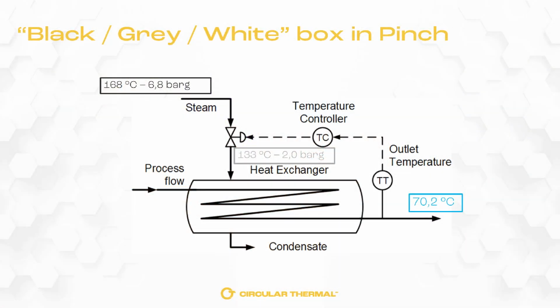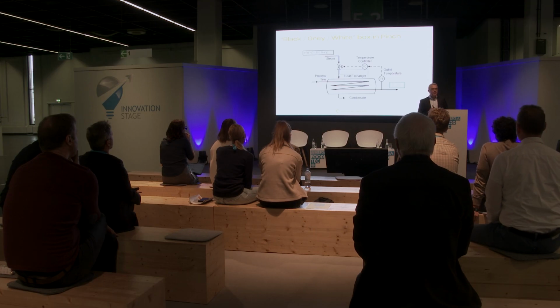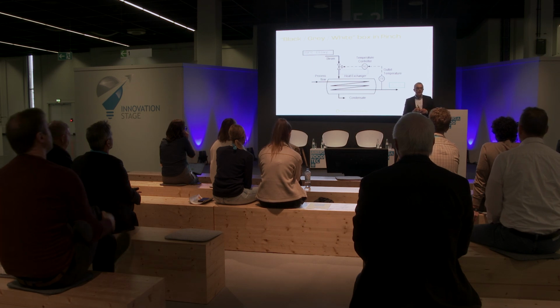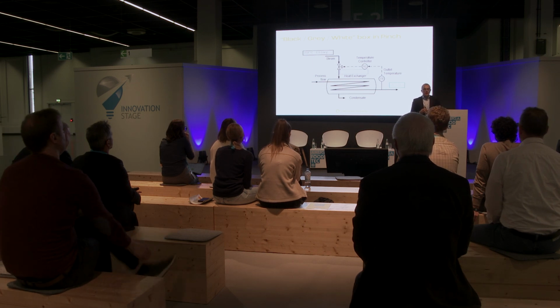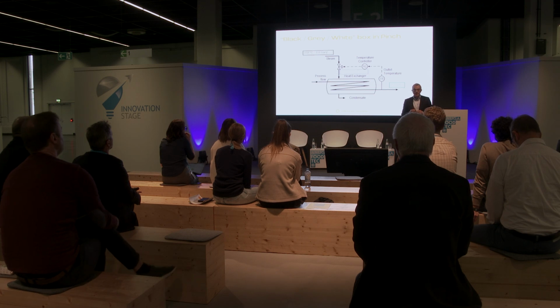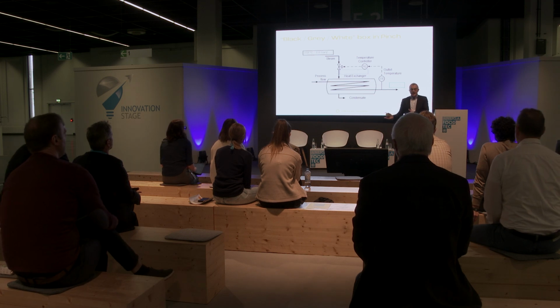Many people look just at the outside - they look at the steam temperature and tell us we need a 180-degree heat pump. The reality is we need to go beyond this black box, as it's called in pinch methodology. We need to go in and look at the temperature in the heat exchanger, and often the 180-degree distribution is actually 120 in the heat exchanger. But then we also need to look at the other side of the heat exchanger.